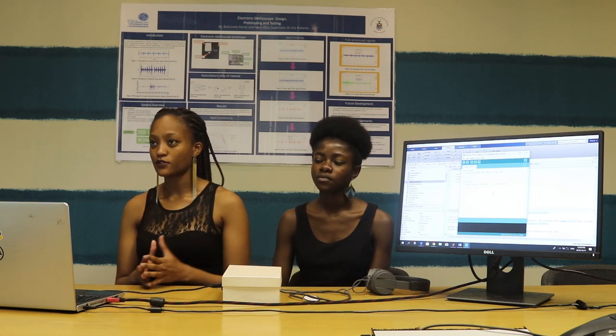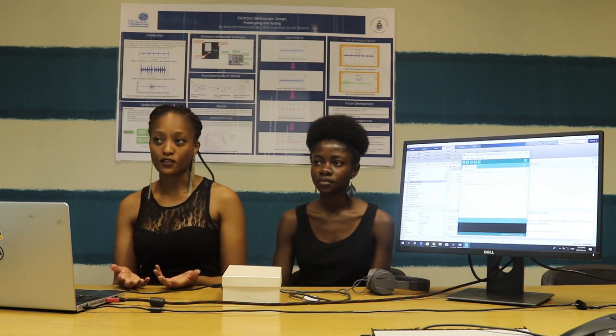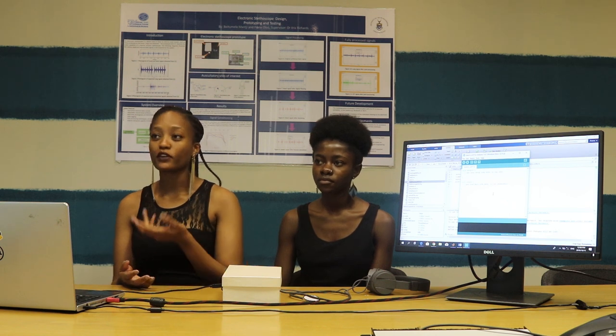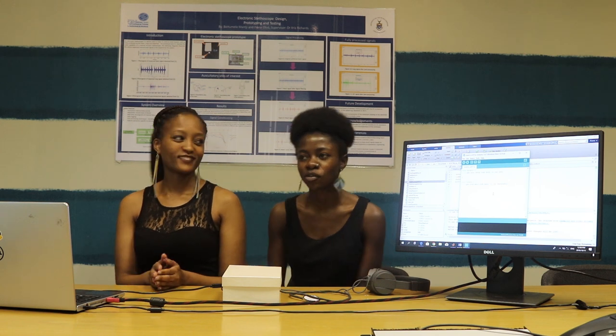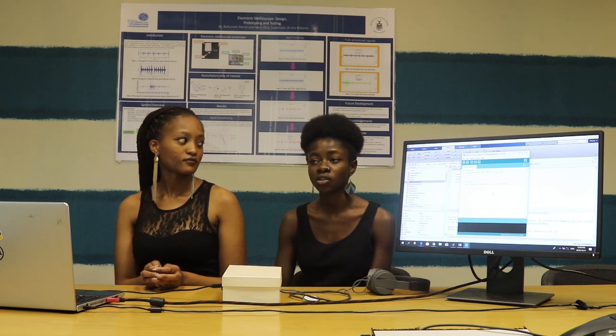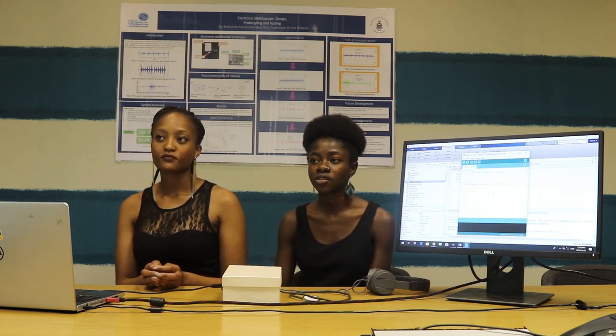For our project we had to develop an electronic stethoscope, which was aimed at improving the functionality of an acoustic stethoscope. This was done through improving the audibility through amplification and being able to standardize diagnostics through things like data logging and feature extraction.